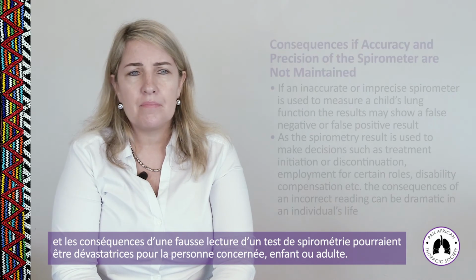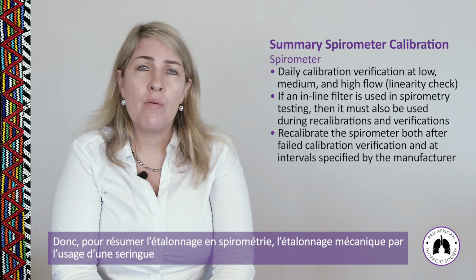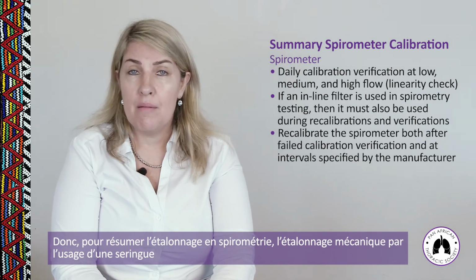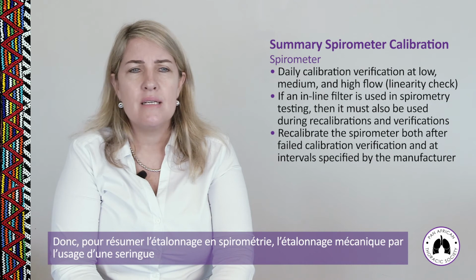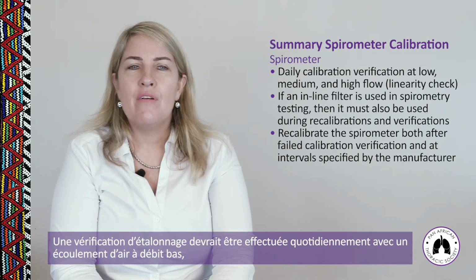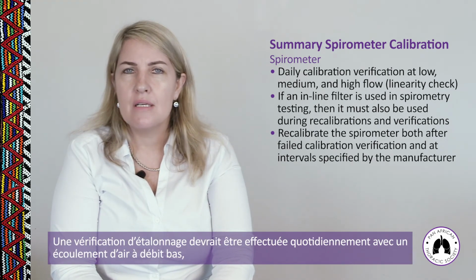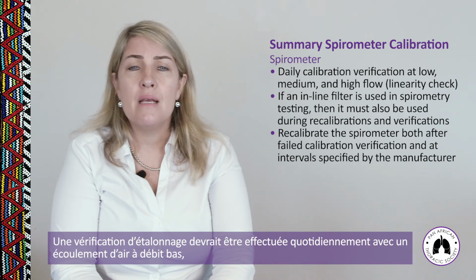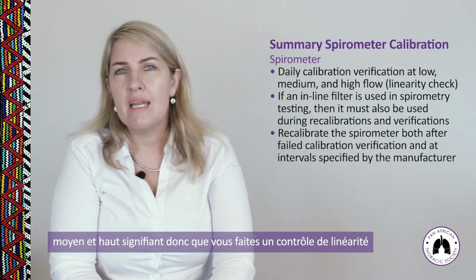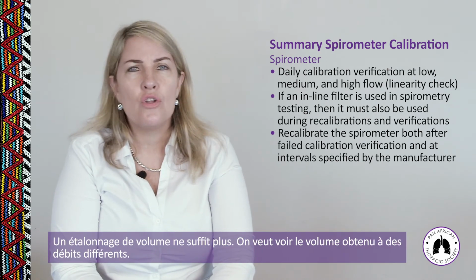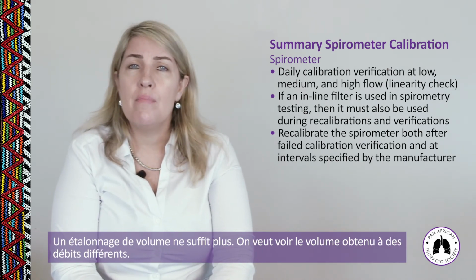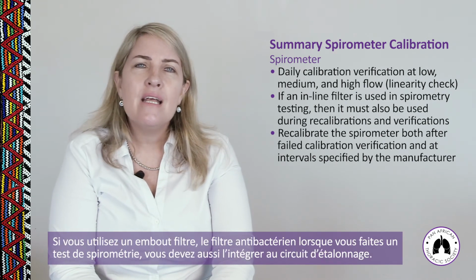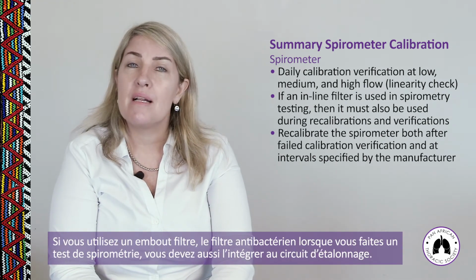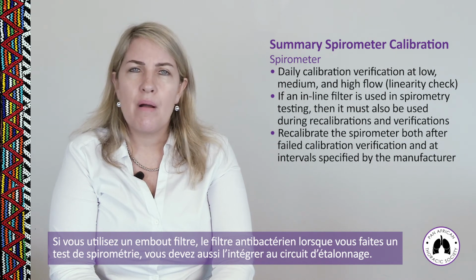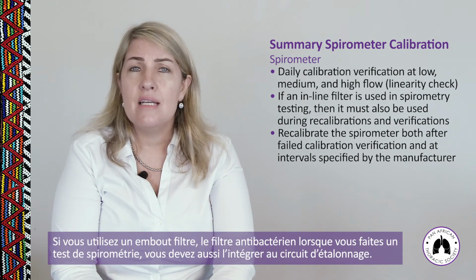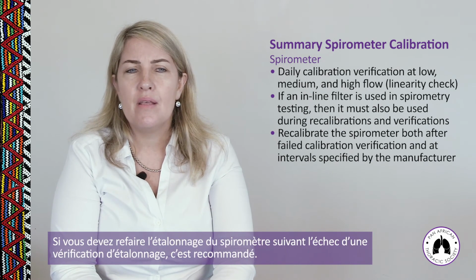So in summary on spirometry calibration, mechanical calibration, that's using a syringe to calibrate, a daily calibration verification check should be carried out with the syringe pumped at low, medium, and high flow rates, meaning you're doing a linearity check. A volume calibration is not enough anymore. We want to look at the volume at different flow rates. If an inline filter is being used, that's a bacterial filter, whilst you are doing a spirometry test, then you must connect that into the circuit when you are calibrating.